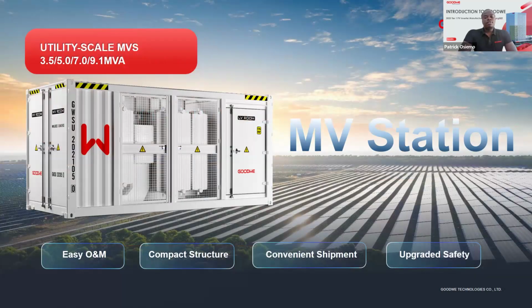Now with the utility scale inverters, because the output is 800 volts, we do have the MV stations. Now we have a number of MV stations available. So in the containerized MV stations, we have the transformer itself. We also have the switch gears for both the low voltage level and the medium voltage level.